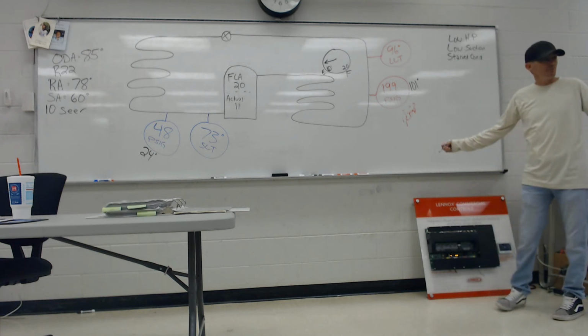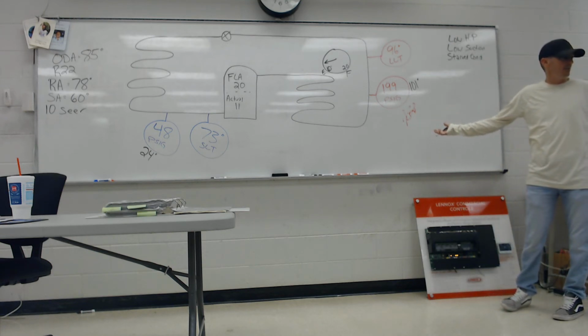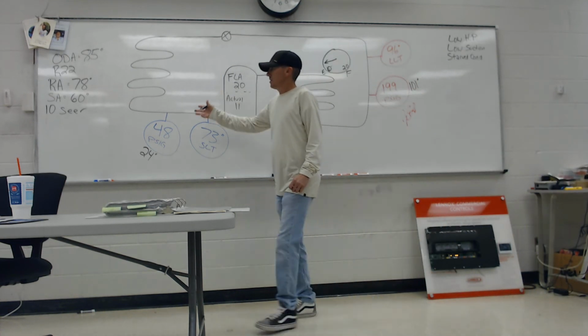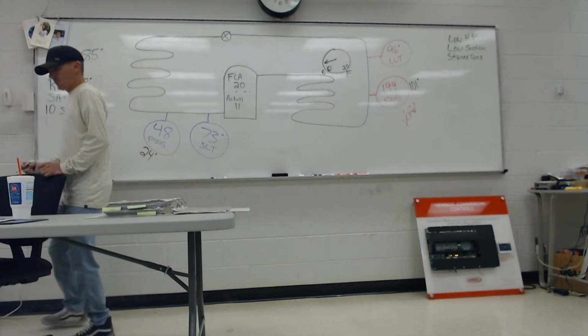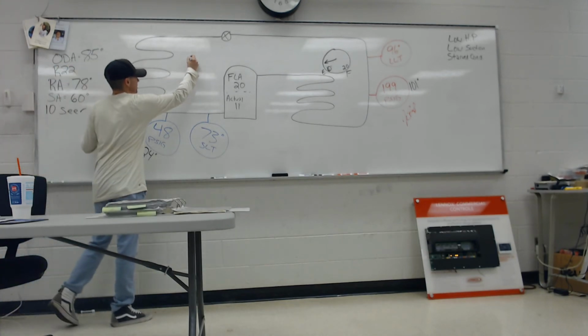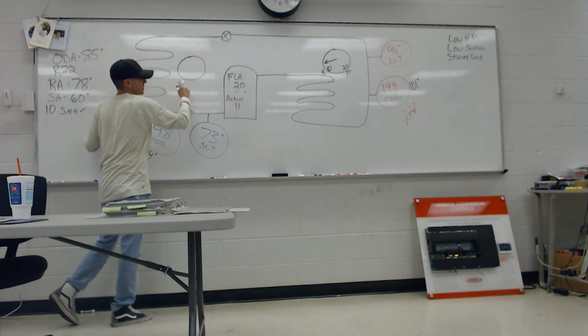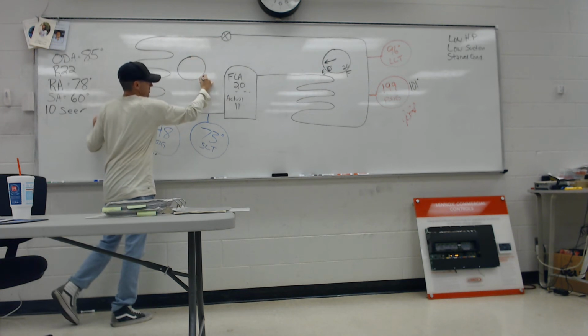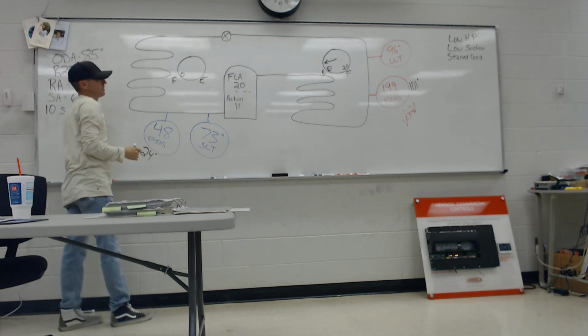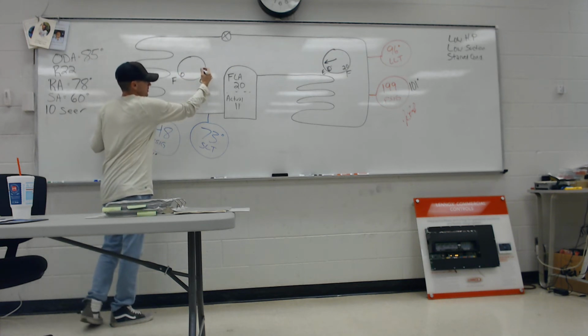So I'm thinking, where's the refrigerant? It's got to be here somewhere. So I start looking at the evaporator. What's my superheat? Superheat is going to tell us the liquid level. Here's my fuel gauge, and remember, superheat is reverse acting. So empty is over here and full is over here at 0. Empty, we'll just say 20 again.